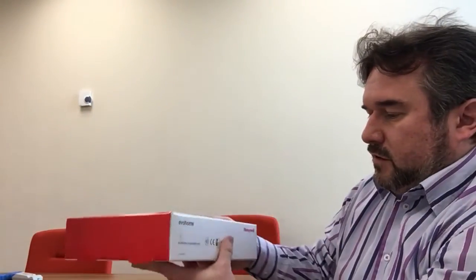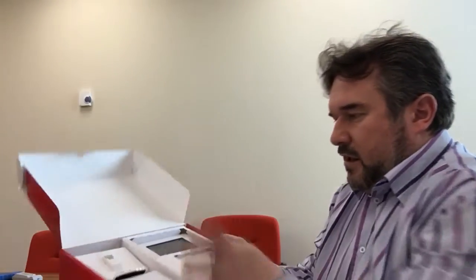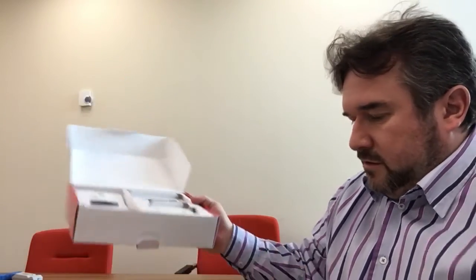So that's how you can make a Honeywell single zone thermostat into a modulating open therm control, and the same applies with any other Honeywell wireless thermostat, including the OFA, the CM927, and of course EVO home. If we open the EVO home box, you'll see that it comes with the BDR-91 relay — just replace that with the open therm bridge and there you go, you've got a modulating open therm thermostat. Thanks a lot!